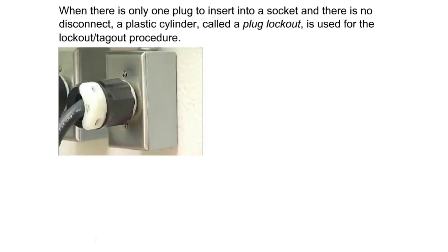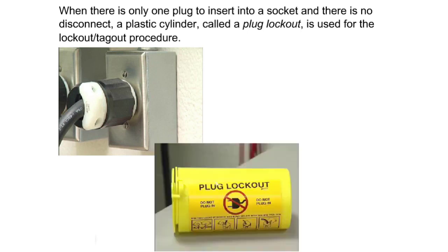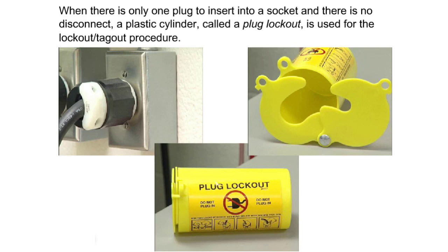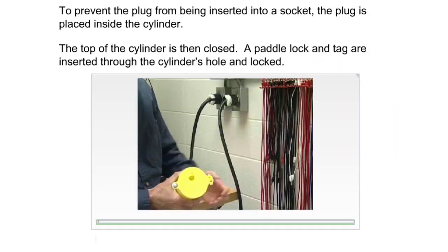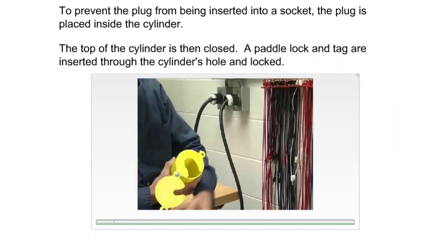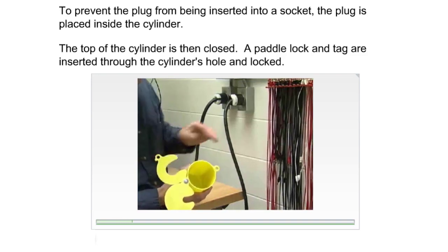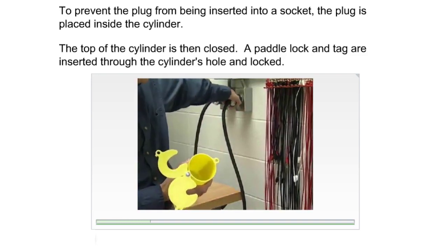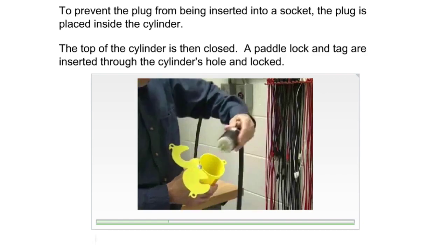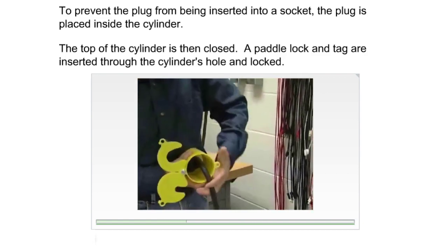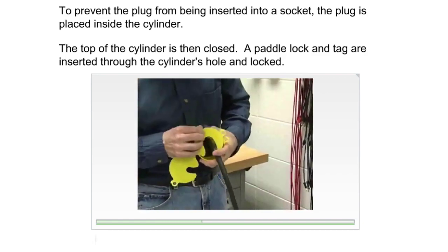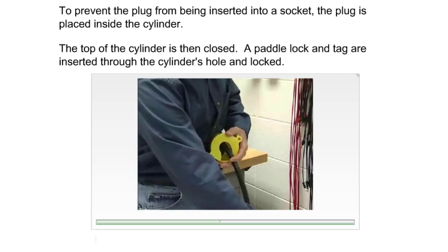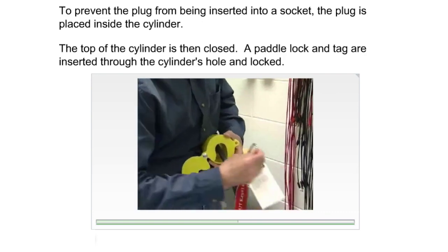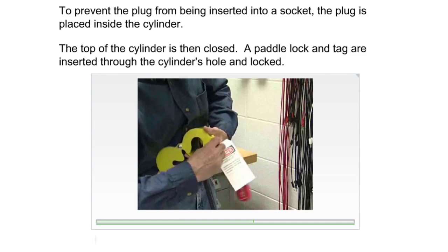When there is only 1 plug to insert into a socket and there is no disconnect, a plastic cylinder called a plug lockout is used for the lockout-tagout procedure. To prevent the plug from being inserted into a socket, the plug is placed inside the cylinder. The top of the cylinder is then closed. A padlock and tag are inserted through the cylinder's hole and locked.